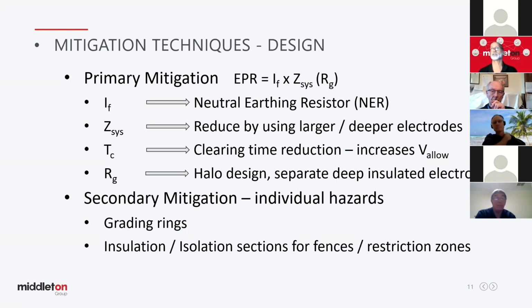So there's many iterations in this calculation because it's a balance between, as you reduce the current, quite often your clearing time then increases, and up and down comes your allowable touch voltage again. So it's a difficult one, but it can be done, and quite often we even bury the EPR.